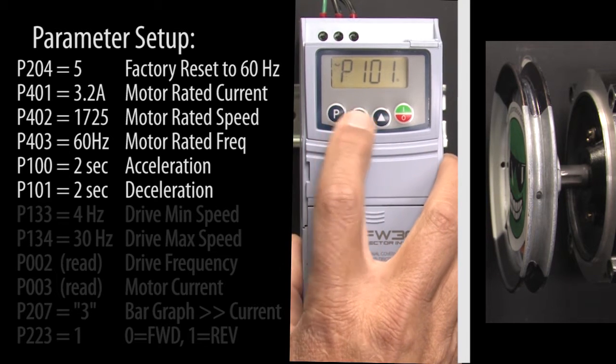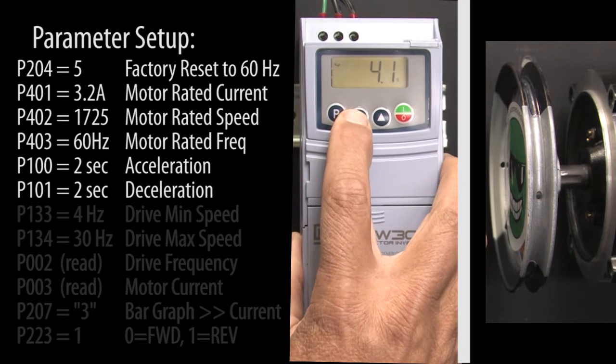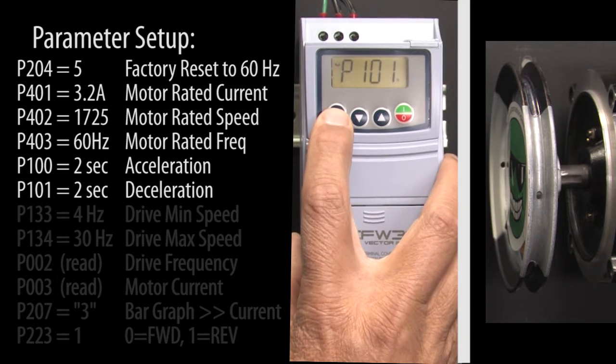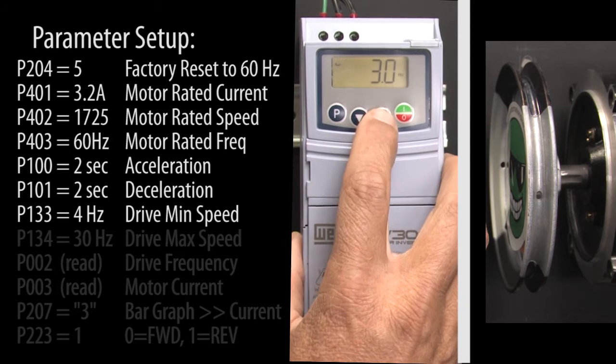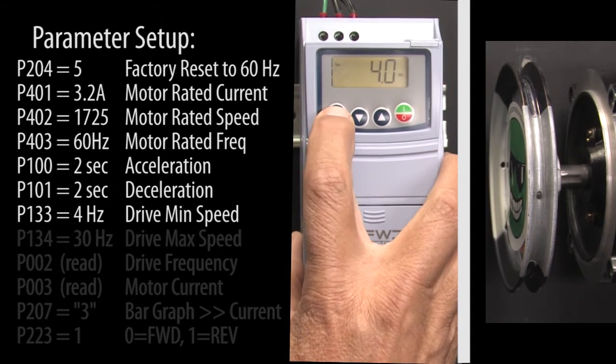Scroll to the next parameter on our list, hit P and change the deceleration to 2 seconds and hit P to accept that. Scroll to the min speed parameter, let's make that 4 Hz. Hit P to accept that.